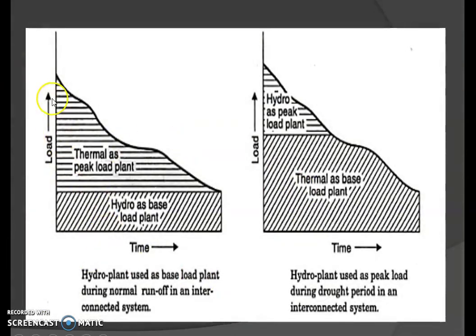Now these curves are again the load duration curves for different categories. In the first curve, the hydro plant is used as a base load plant, whereas in the second curve, the thermal plant is used as a base load plant and hydro is used as the peak load plant. Here again we see that the highest load is covered first, then the lowest. That means in the load duration curve, the peak loads are plotted first, that is, the load is plotted in descending order.